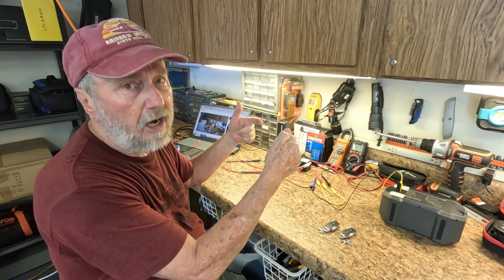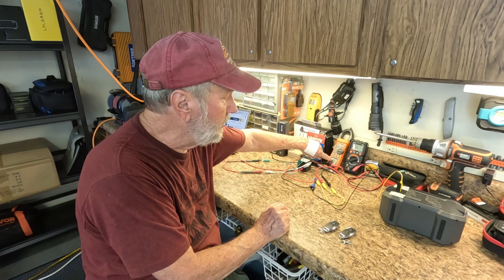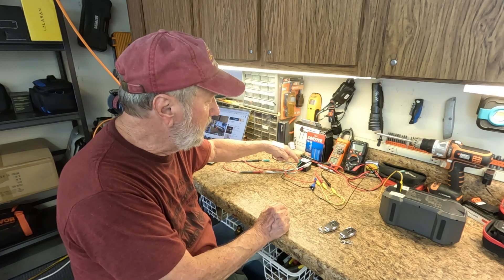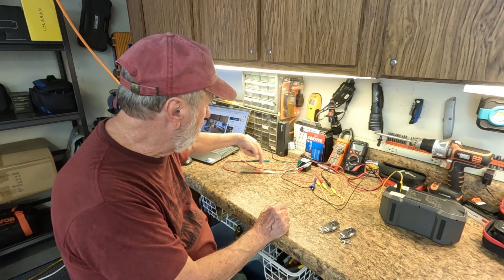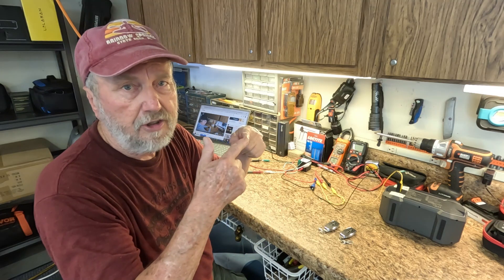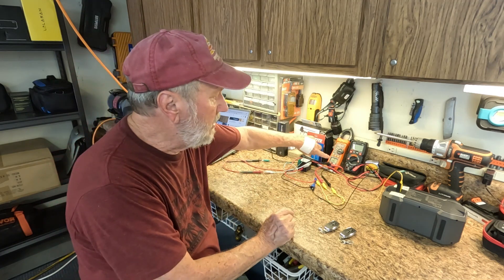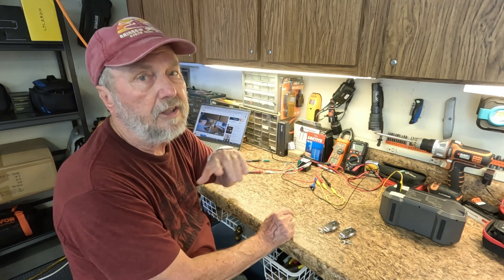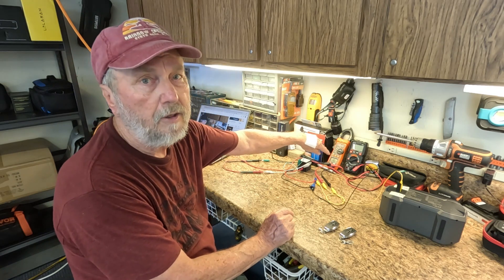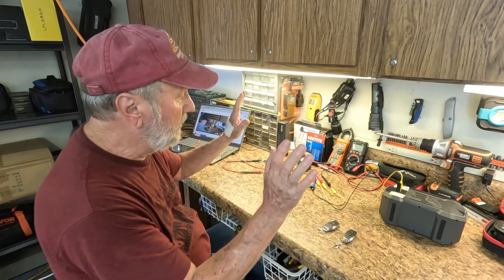The relay is not operated, so it's going to be open — no current is flowing. Right now, this is measuring resistance. Those relay contacts are not closed. The red, green, and white go to these leads over here, and polarity doesn't matter — resistance is just measuring continuity. It's either open or closed. Right now, O.L means it's open. The relay is not operated. You'll see this meter show an indication when I operate the remote and operate the relay.